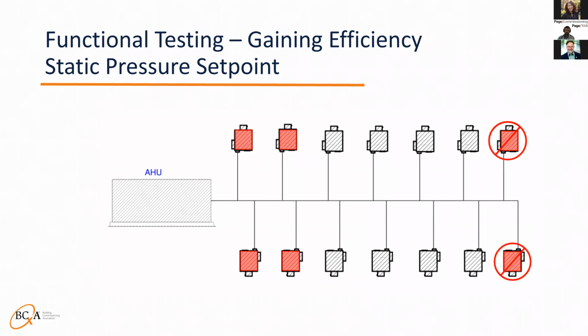If you find that one box has issues getting its air, it may not be worth bumping the static on the AHU just for one box, especially if you have to add 1/4 or 1/2 inch to your set point.